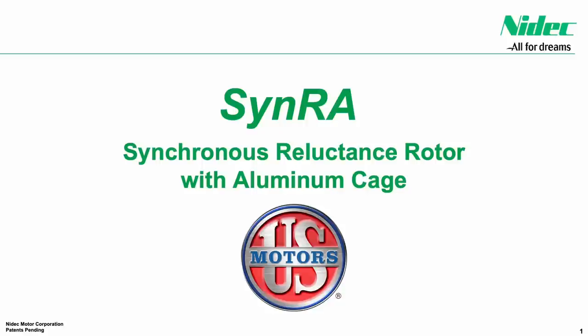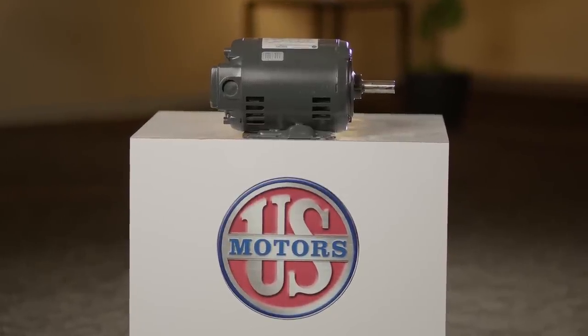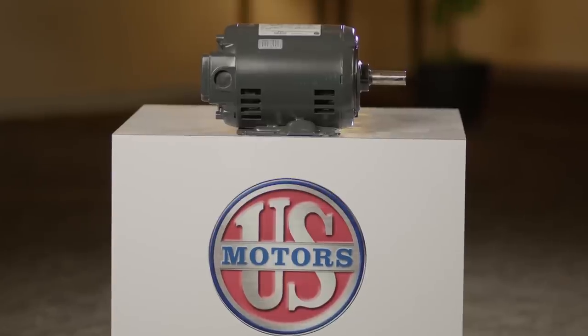SynRA utilizes an aluminum cage in a synchronous reluctance rotor lamination, allowing the motor to start like an induction motor but run as a synchronous machine, taking advantage of both technologies' benefits.